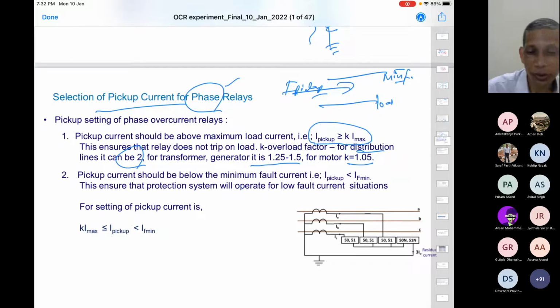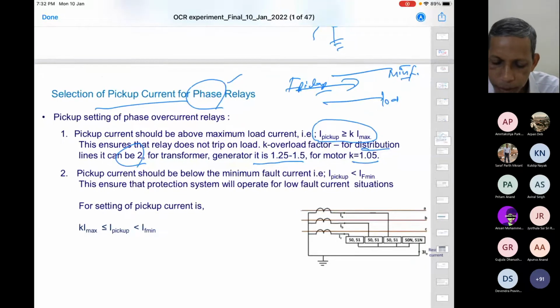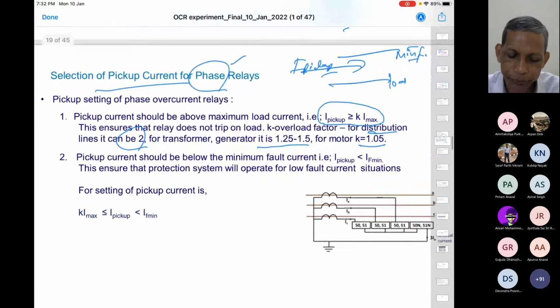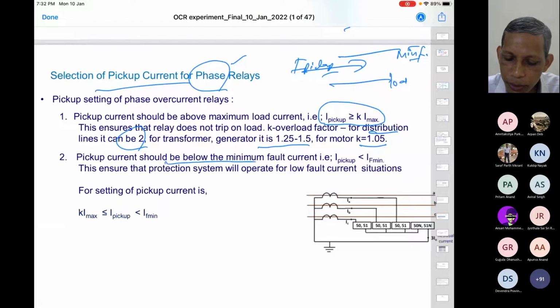But this is a general guideline. This does not hold good always. There are situations where it may not be correct. But still, let us go by that. So pickup current should be below the minimum fault current, as I say. That is also another guideline. So this ensures the protection, you can say, will be like this.